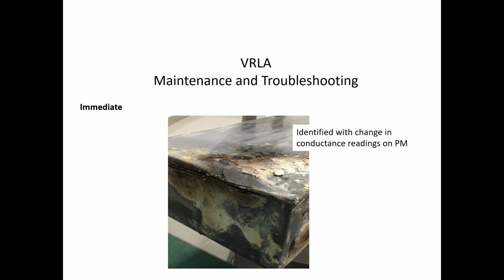Something happened during installation, and then there was a ground fault. There was a crack. There was a path to current. With an ohmic value, we could see the cell was heating up, drying out. Now, because of the steel tray, there was no real indication of temperature. It was probably warm about the back of this and would have been picked up on infrared thermography. But this rack was up against a wall, so we had no way of actually detecting that.